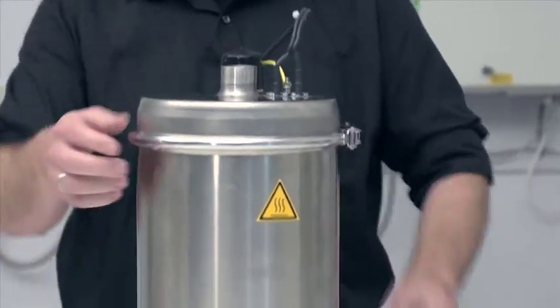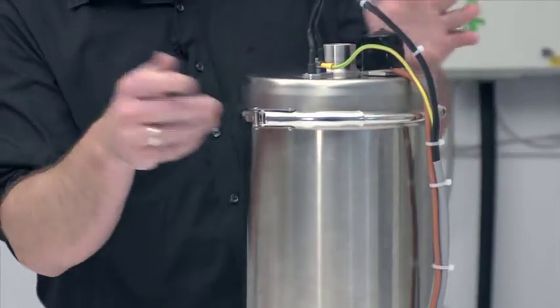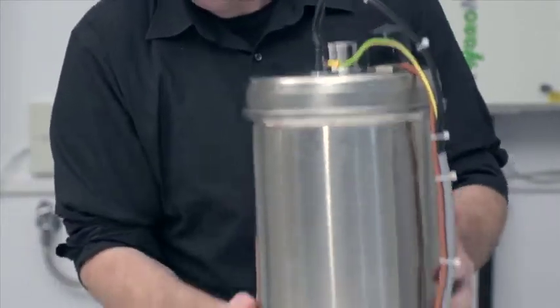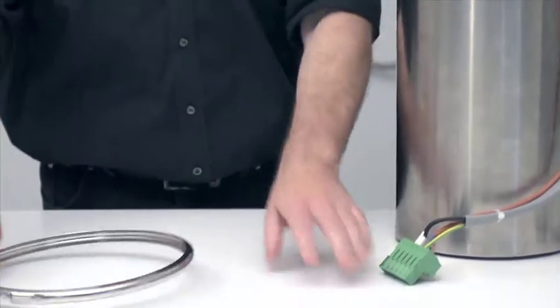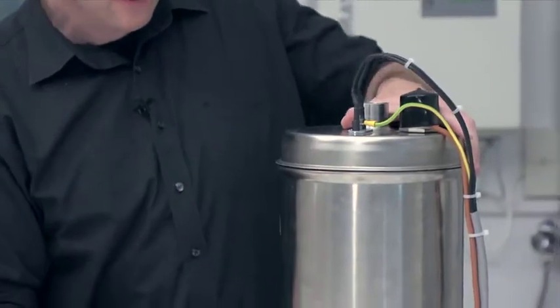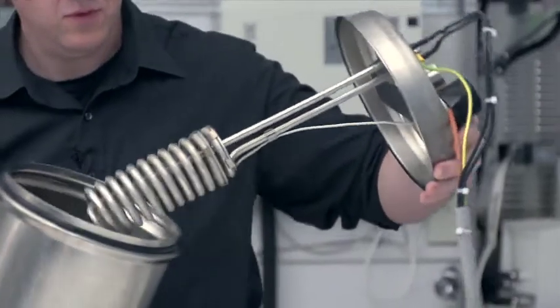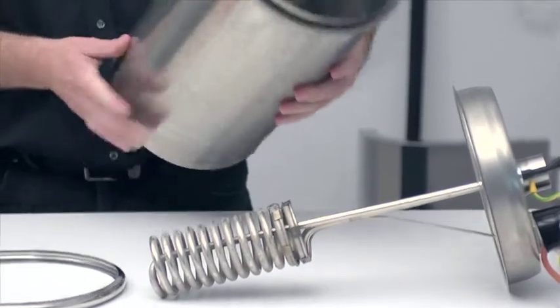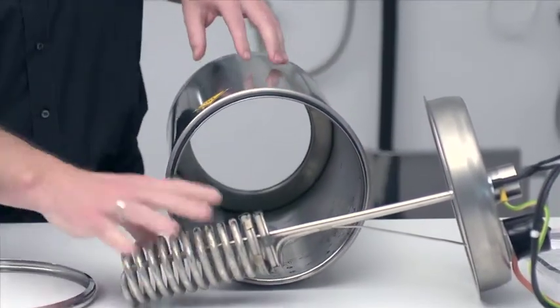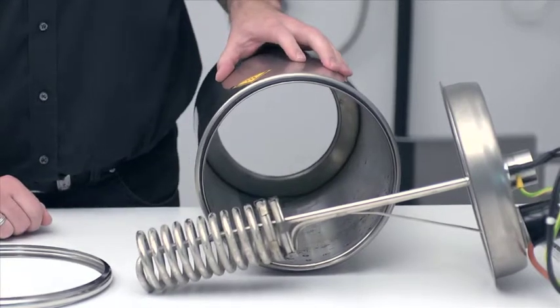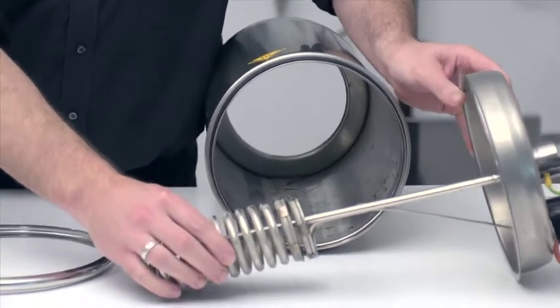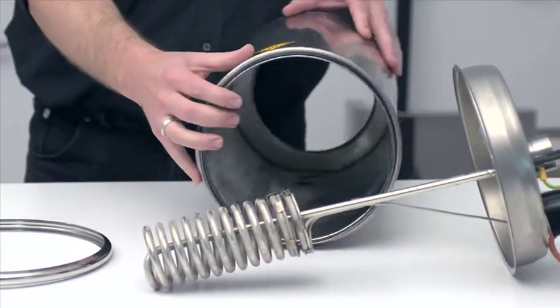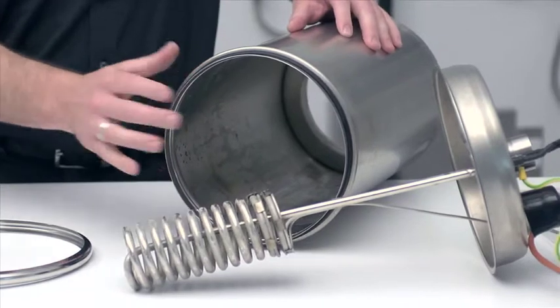For cylinder maintenance we open the cylinder on top at the clamping ring. Then we can pull up the cylinder top and have the heating element out as well, which is connected to the cylinder top. You can tell that both the heating element and the cylinder still look very good. There is very little calcium residue. Normally you would find a little more, which of course all depends on the length of time the steam humidifier has been in operation.